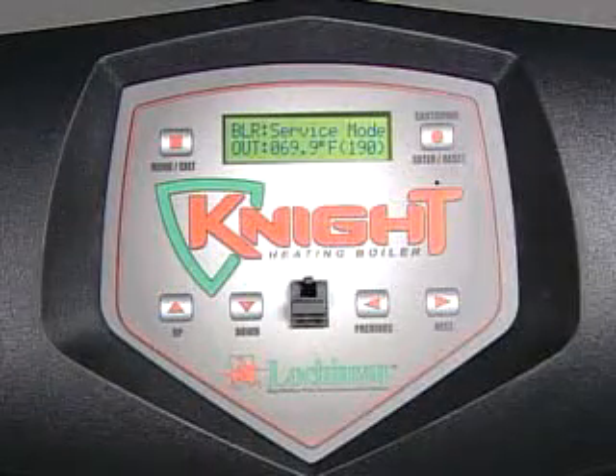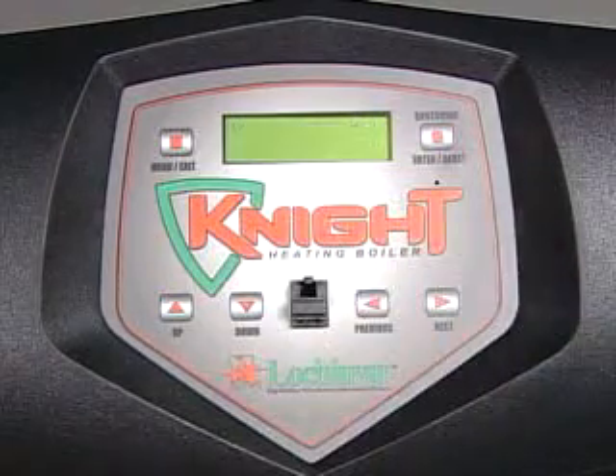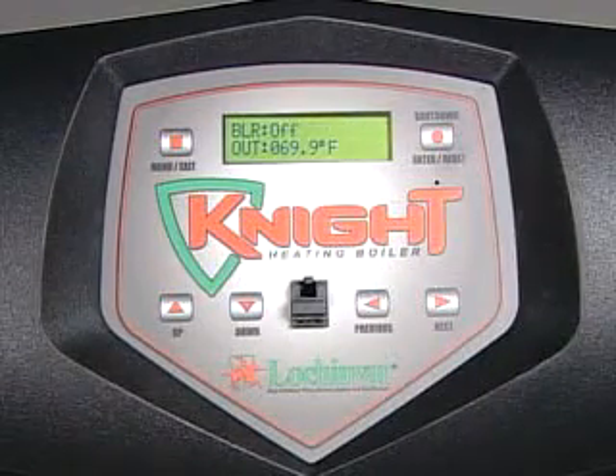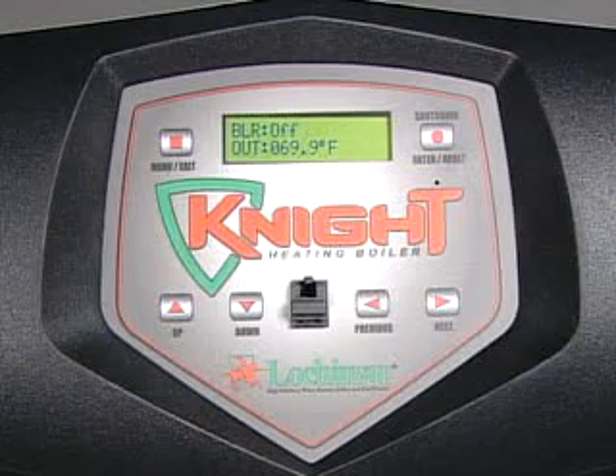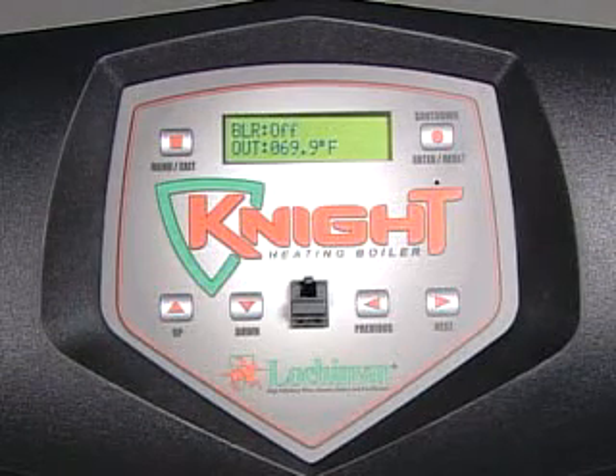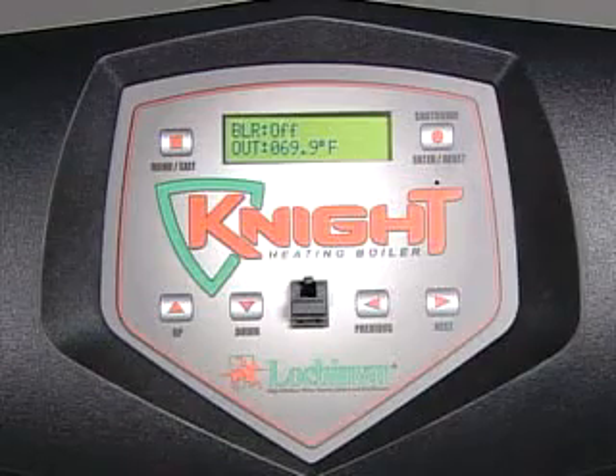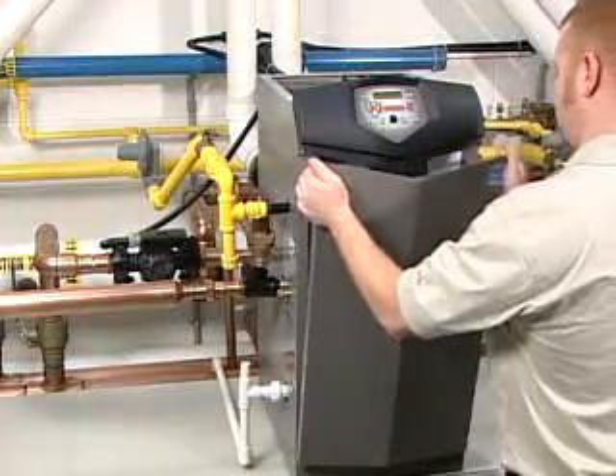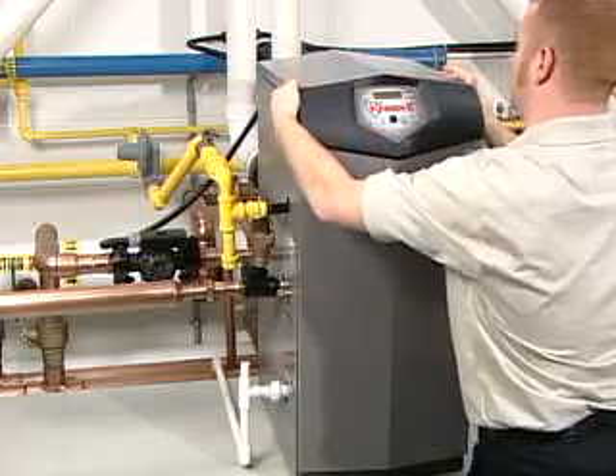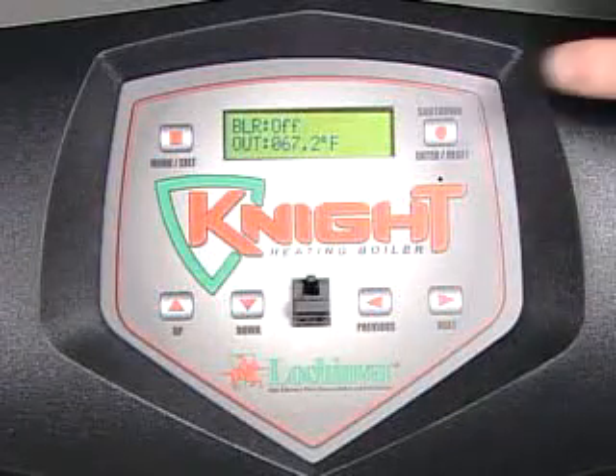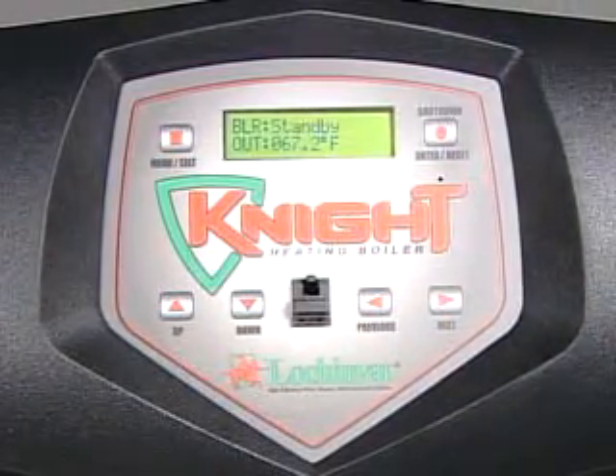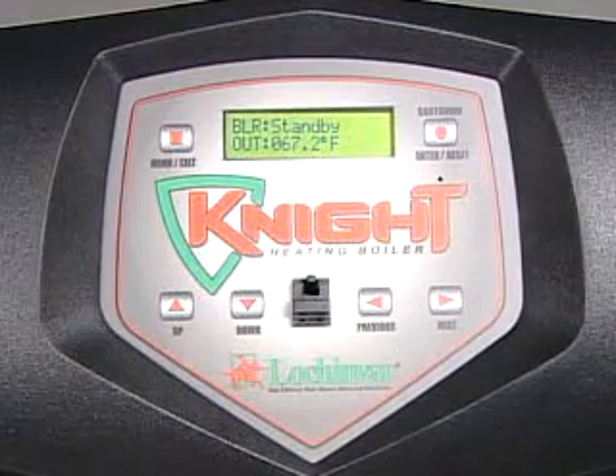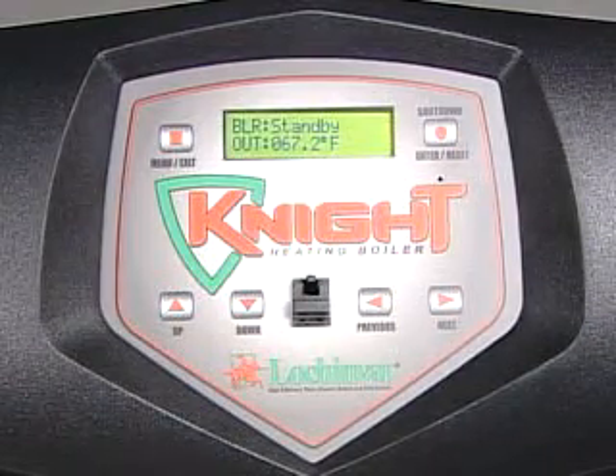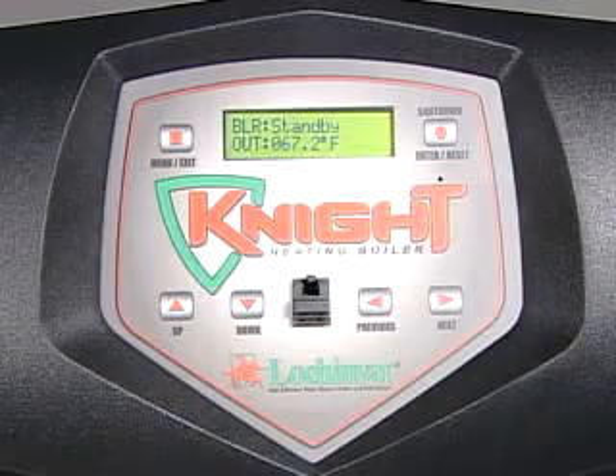Once the testing is complete, press the Shutdown Enter Reset button one time to take the unit out of service mode. The unit will shut down and boiler off will be shown on the first line of the display screen. Replace the top and front panels on the unit. Press the Shutdown Enter Reset button until Boiler Standby is shown on the first line of the display screen. The unit is now ready to accept a heat demand.